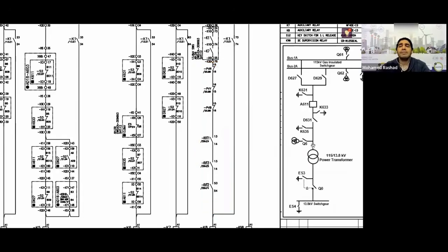Okay, so what is this part, engineer? This part tells you how to know if the breaker on the other side, or all the things we are talking about, are in a very simple situation. I look through the voltage transformer to see if the voltage is live or dead. But who told you that the voltage transformer is working properly? Isn't it possible that the feed isolator is open? Isn't it possible that the feed MCB in the box above is open? Isn't it possible that the feed MCB in the LCC is open? You told me yes, so I need to check all of these, right?